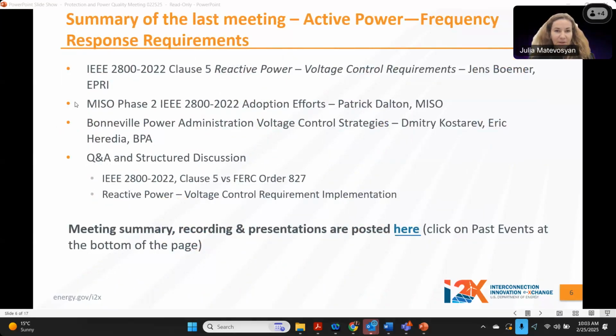Just as a summary of the last meeting, we had a meeting on voltage control requirements. So we spoke about clause 5 of IEEE 2800. Jens presented on that, then MISO presented phase 2 of the IEEE 2800 2022 adoption efforts. Patrick Dalton spoke to that. BPA presented their voltage control strategies, and then we had Q&A and structured discussion around IEEE 2800 Clause 5 versus FERC Order 827 requirements, and also implementation of reactive power voltage control requirements. You have a meeting summary, recording, and presentation posted on the DOE i2X first webpage. Once we share the slides, you can also have a direct link.